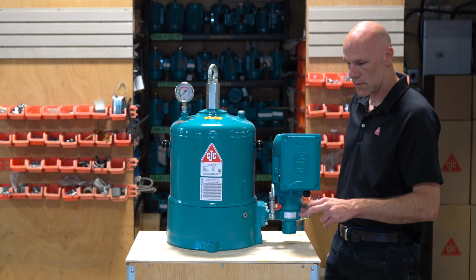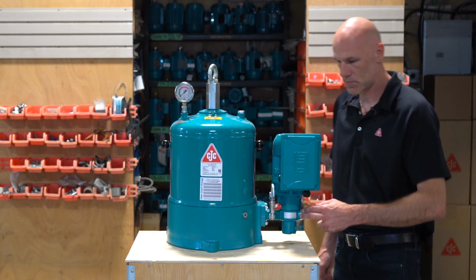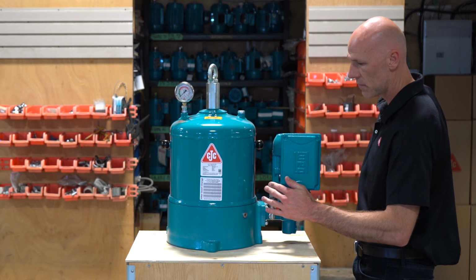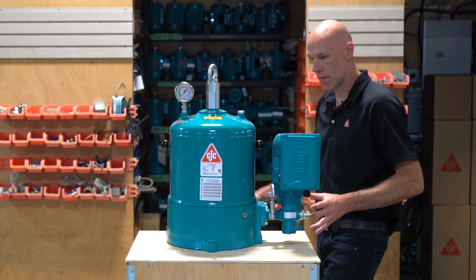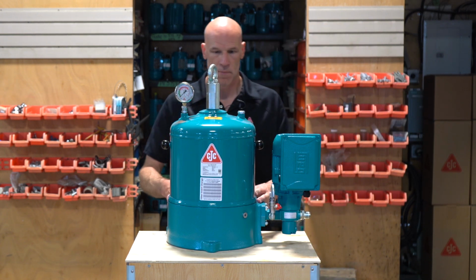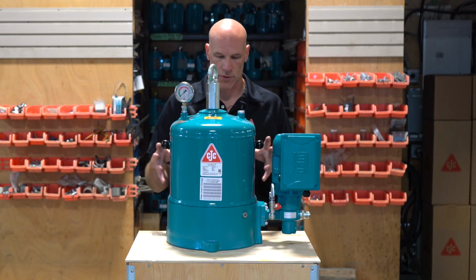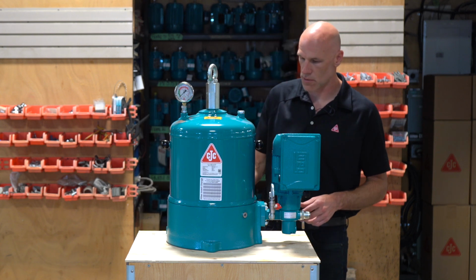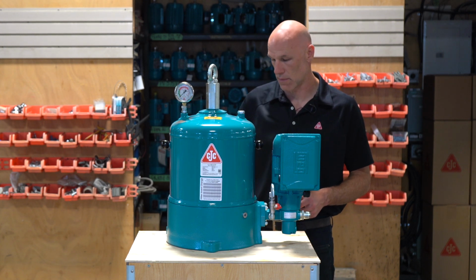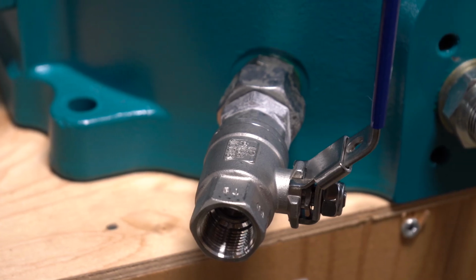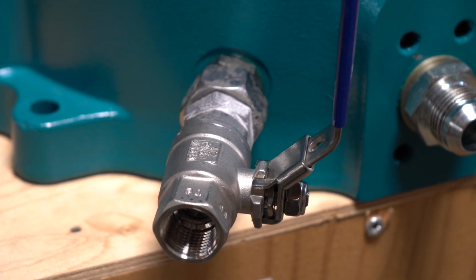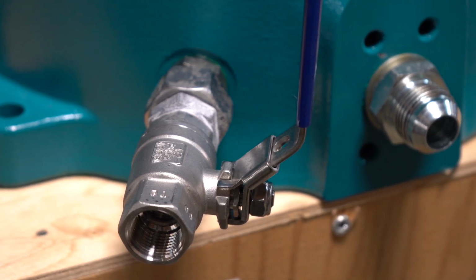The oil is drawn in through the pump suction port, past the pre-filter sample valve, and then is pushed into the filter housing. From there, the oil travels through the filter insert, down through the core, and then to the filter outlet. When you're doing a filter change, you can use the drain valve to drain the oil out of the housing before opening it up.